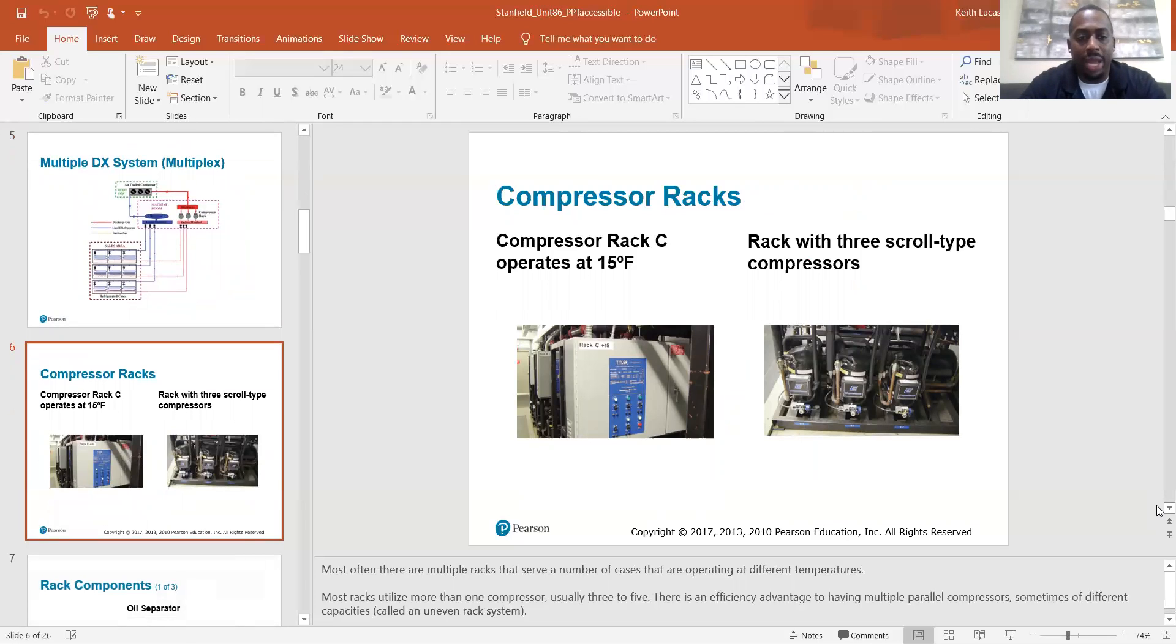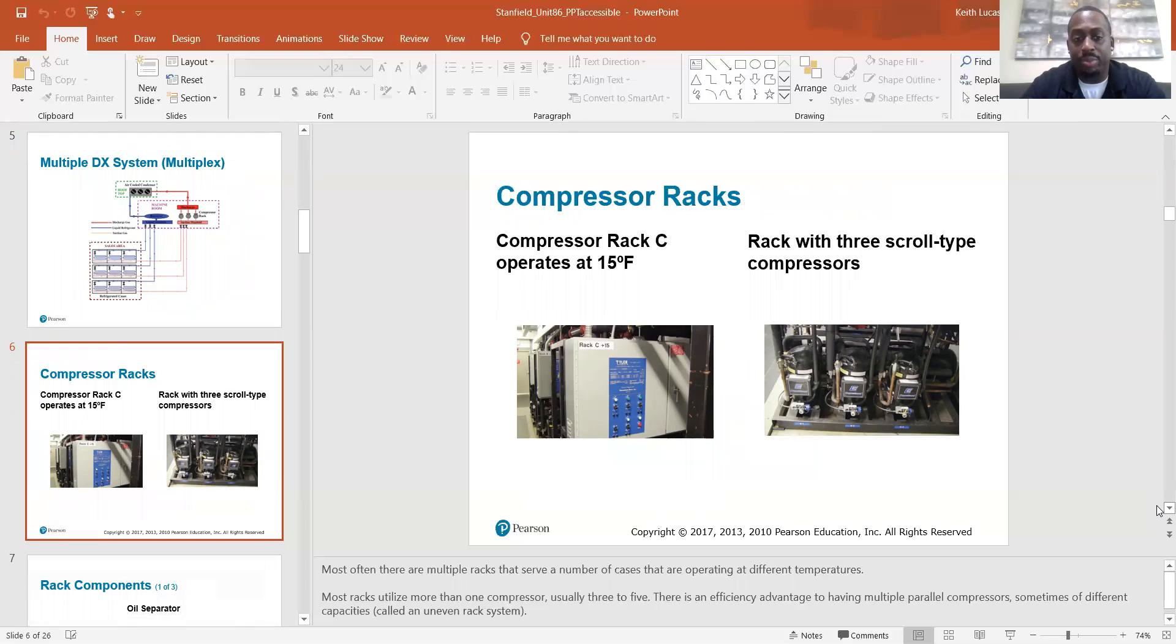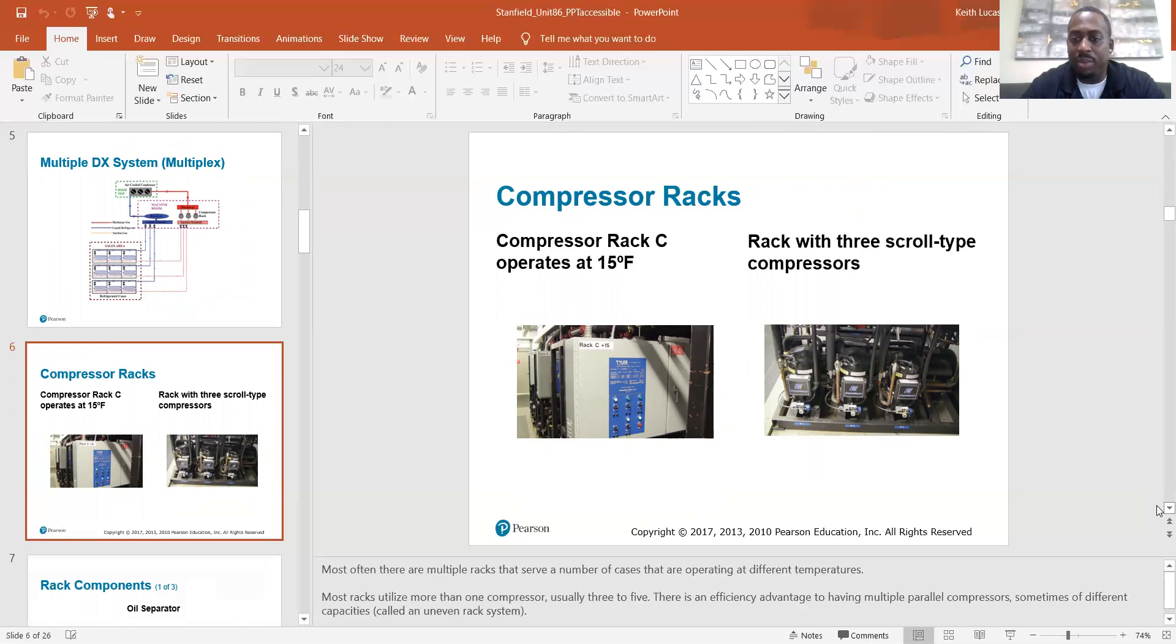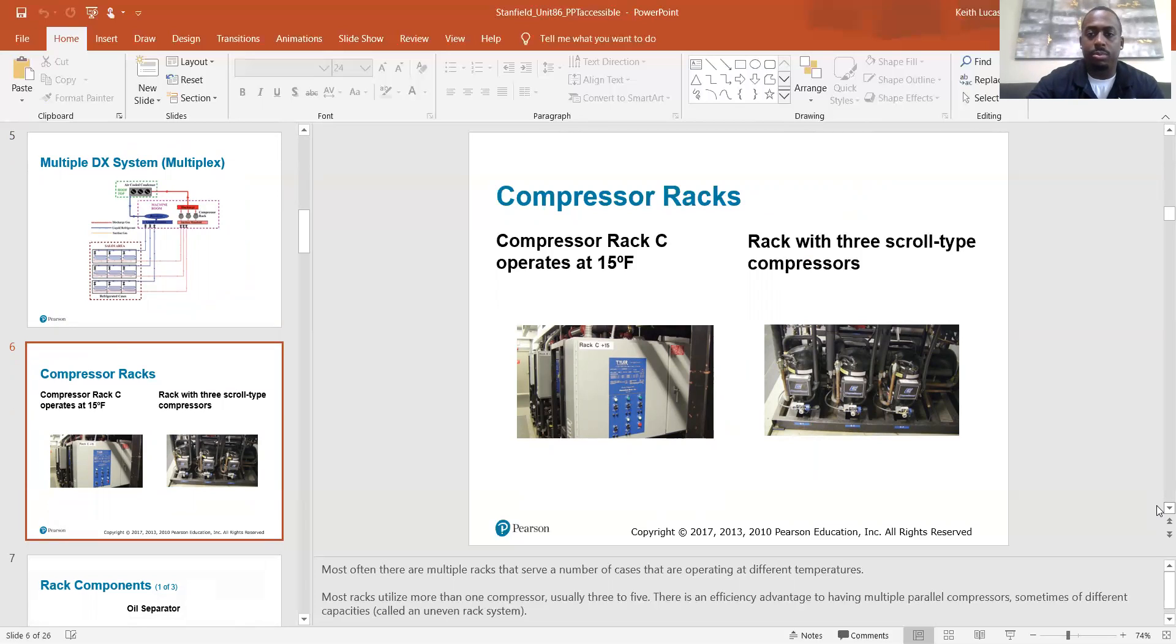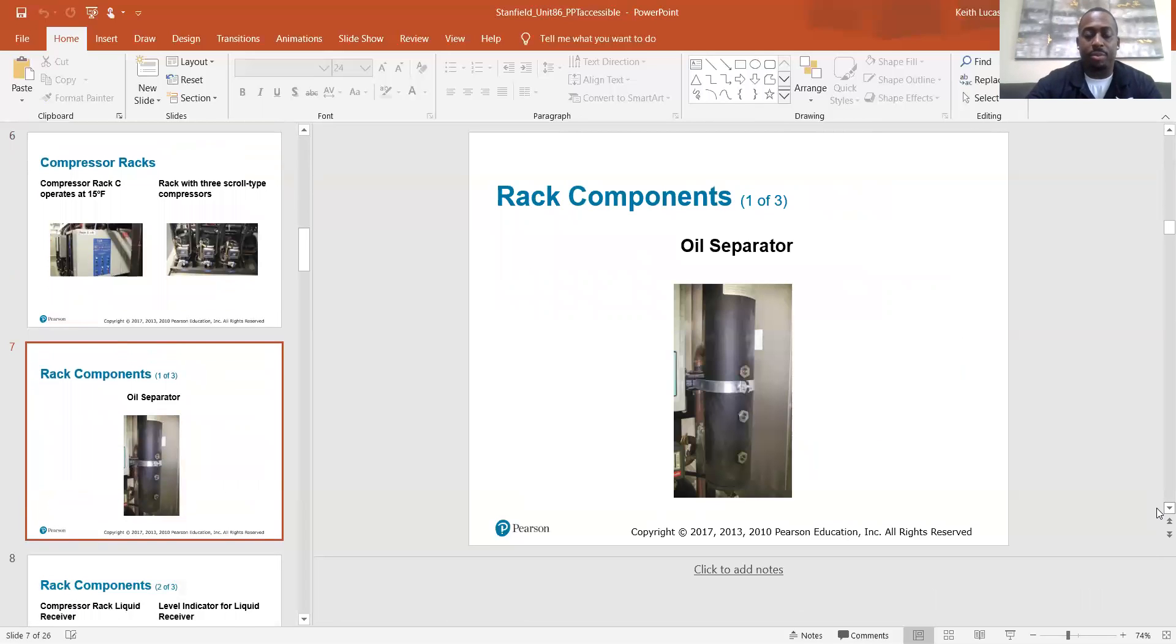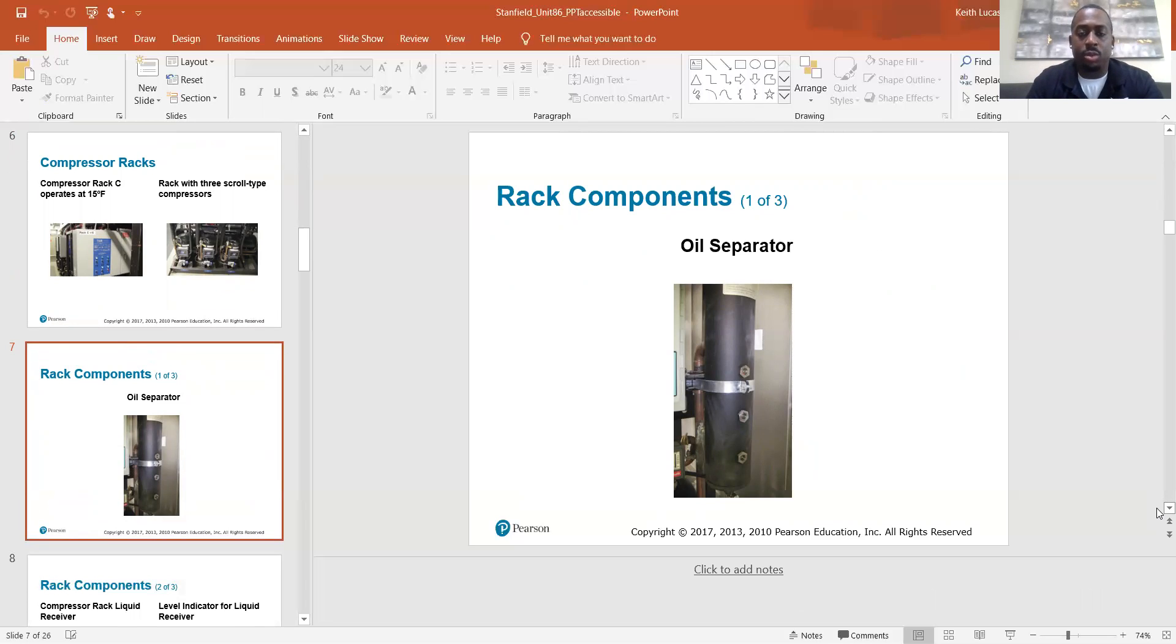Compressor racks. Most often there are multiple racks that serve a number of cases that are operating at different temperatures. Most racks utilize more than one compressor, usually three to five compressors. There is an efficiency advantage to having multiple parallel compressors, sometimes of different capacities called an uneven rack system. With uneven rack systems, you can operate at a range of capacities based on the needs.